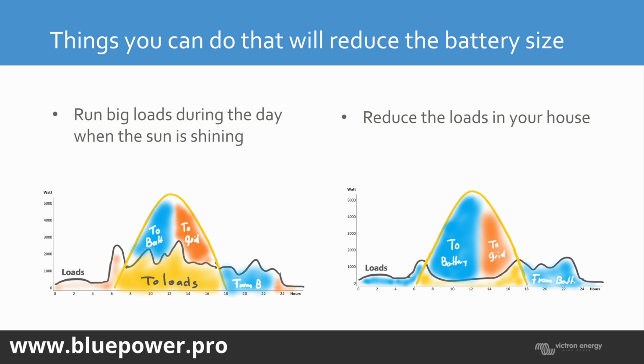You're going to run from your batteries probably from about 4 o'clock in the afternoon till about 8 o'clock the next morning. So that's 16 hours. So that's going to be 70% of your loads is going to be mainly battery, or running from the battery, depending on how you optimize your loads. So if you run more loads during the day, you can bring that down so that you only use maybe 30 or 50% of your load during nighttime.